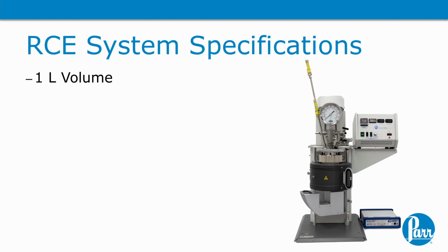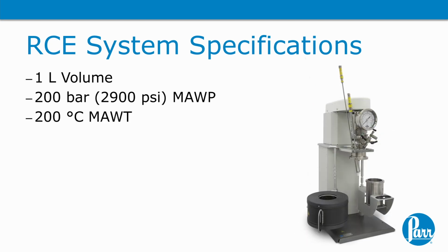The RCE system that is being offered by our company is a stirred pressure reactor system based off of our 4520 series reactors. The system has approximately a 1 liter volume, with a maximum allowable working pressure of 2900 psi and a maximum allowable working temperature of 200 degrees C because of some of the components that are part of this system. It will have alloy C276, also known as Hastelloy C, as the material of construction for the surfaces contacting the liquid phase of the system.